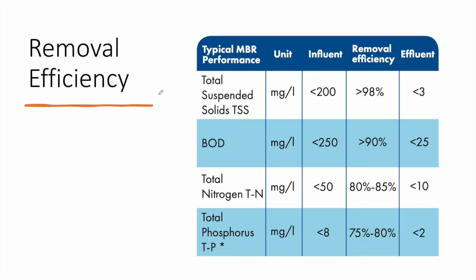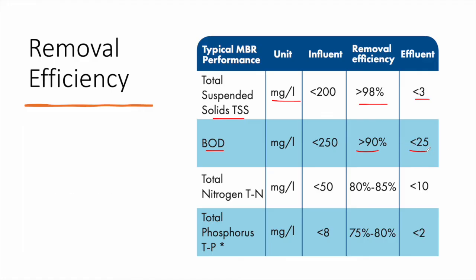Regarding removal efficiency, we have very high reduction of total suspended solids. If your influent is less than 200 mg/L, you can expect 98% removal of TSS, giving an effluent of less than 3 mg/L — a very clear effluent. We also have high reduction of BOD greater than 90%; if the influent has around 250 mg/L of BOD, you can expect a BOD less than 25 mg/L. Additionally, high reduction of total nitrogen at 80–85% and high reduction of total phosphorus at 75–80%. You can meet most international and national standards easily.